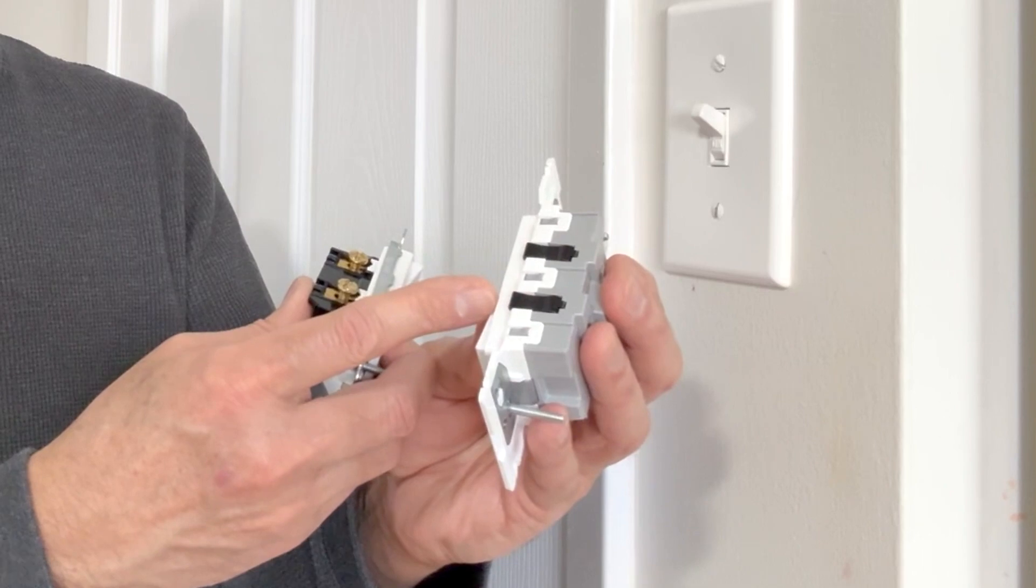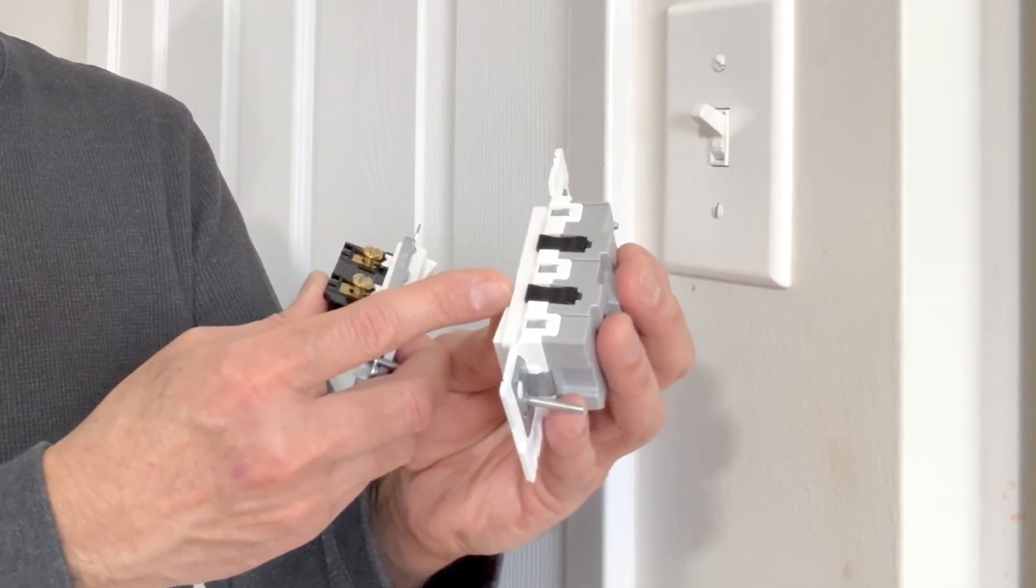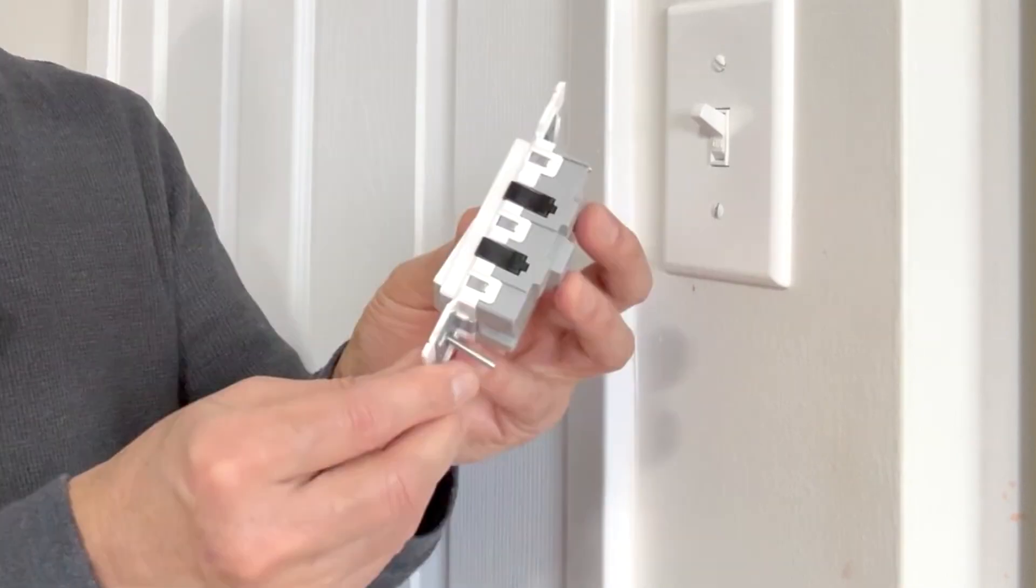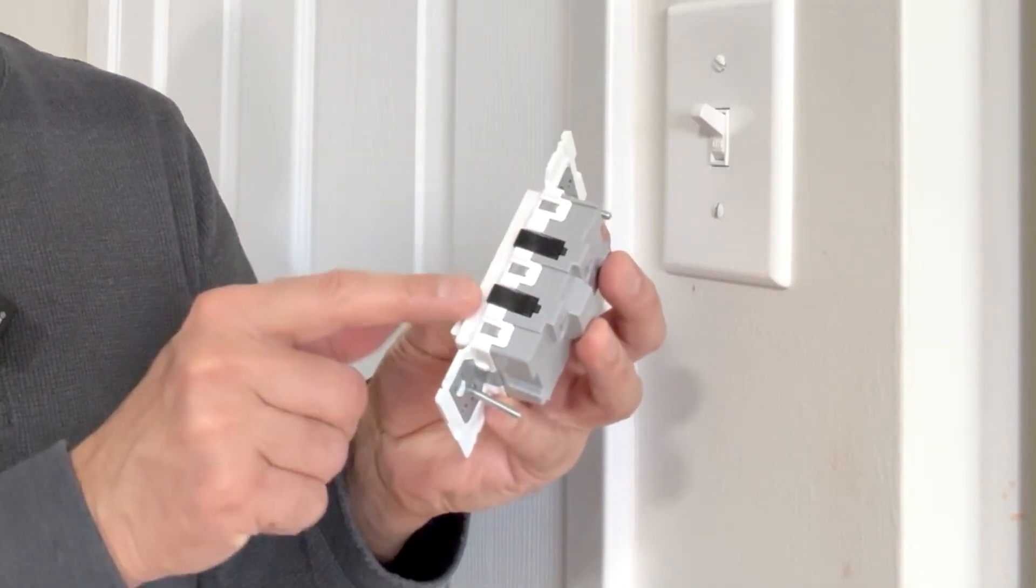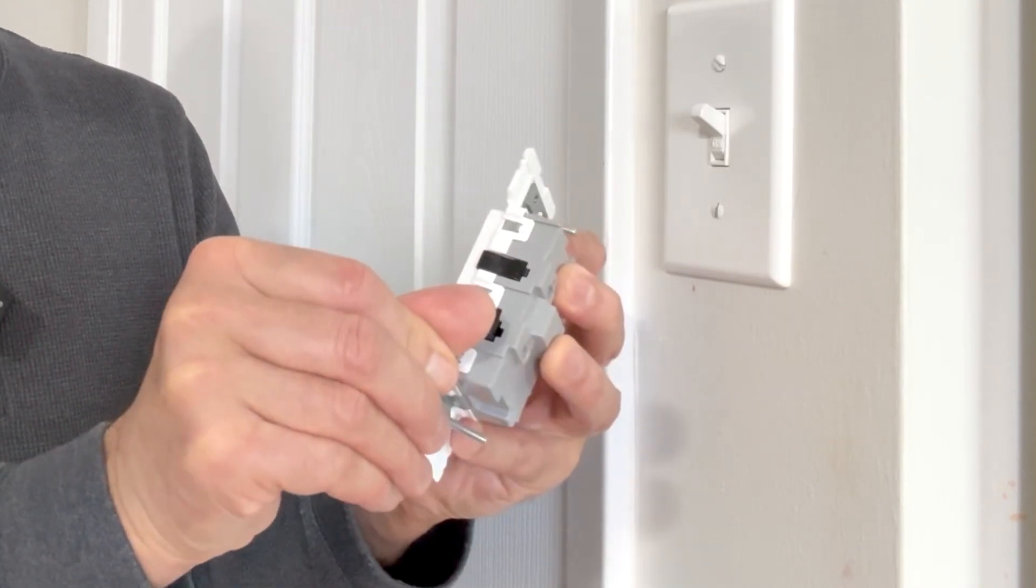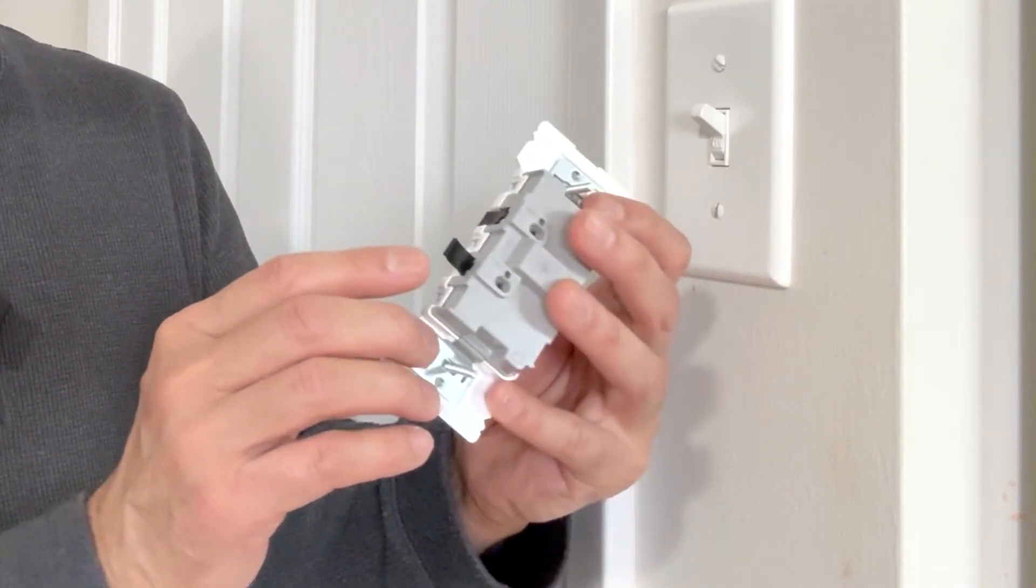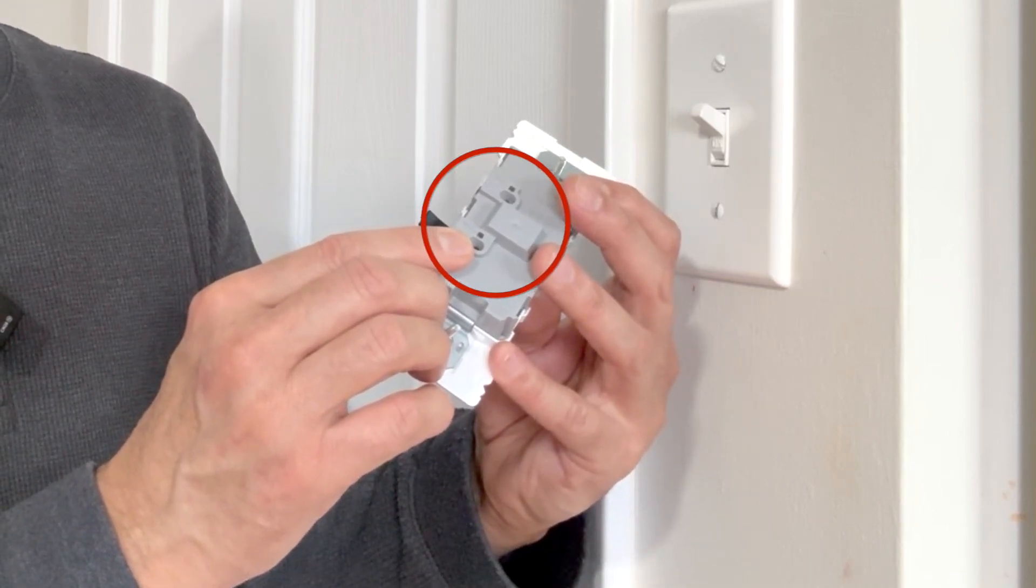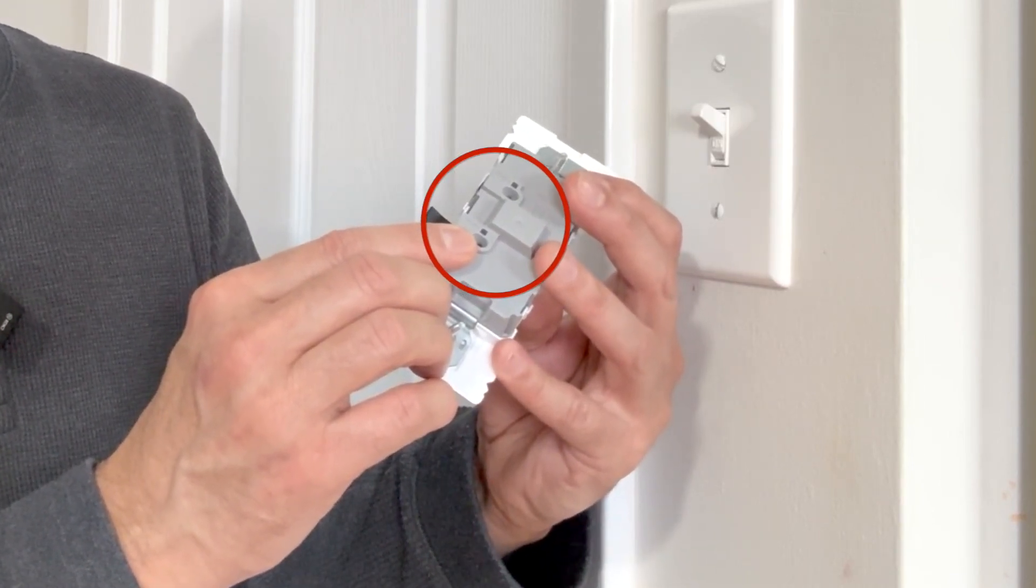These connectors are very similar to Wago style lever nut connectors but I would say they are much stronger than the Wago lever nut connectors. So as I said there are no exposed metal parts, there are no screws to which you tighten the wires. Pull out the lever, insert the wire on the back side. This is not like backstabbing, this is actually called back wiring, not backstabbing.